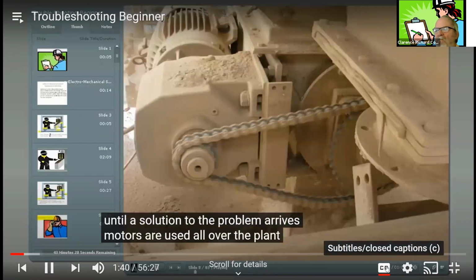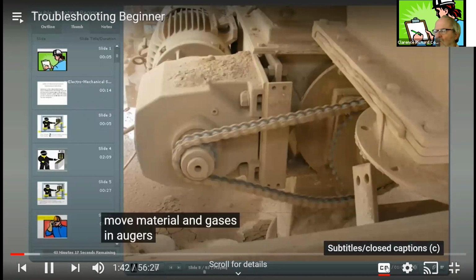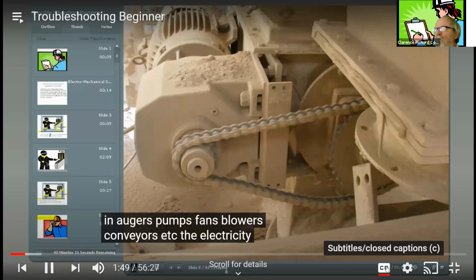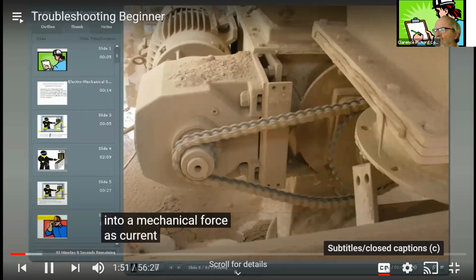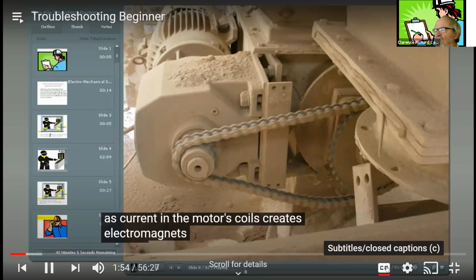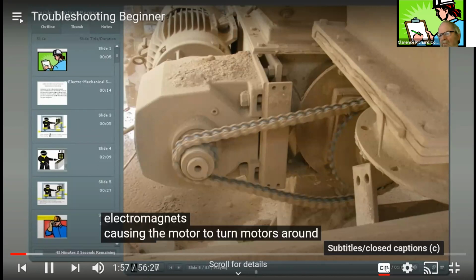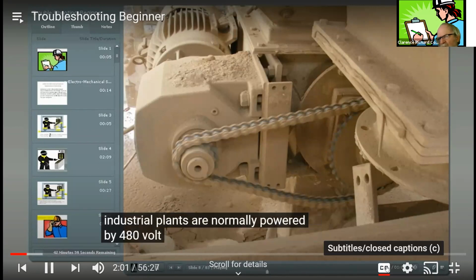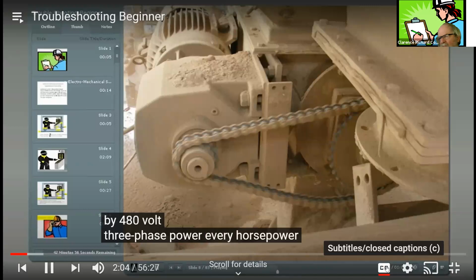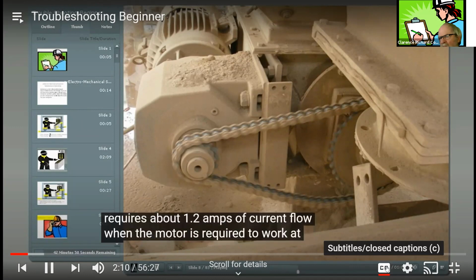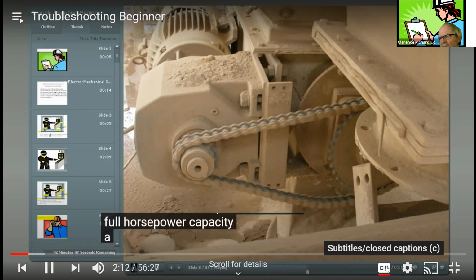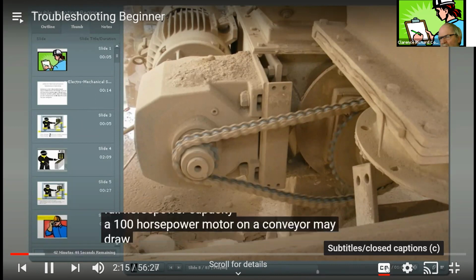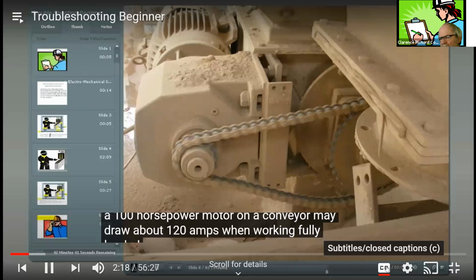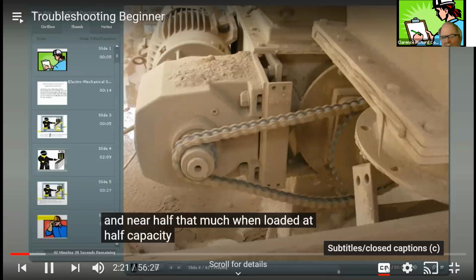Motors are used all over the plant to move material and gases in augers, pumps, fans, blowers, conveyors, etc. The electricity is turned into a mechanical force, as current in the motor's coils creates electromagnets, causing the motor to turn. Motors around industrial plants are normally powered by 480-volt, three-phase power. Every horsepower of a motor requires about 1.2 amps of current flow when the motor is required to work at full horsepower capacity. A 100 horsepower motor on a conveyor may draw about 120 amps when working fully loaded, and near half that much when loaded at half capacity.